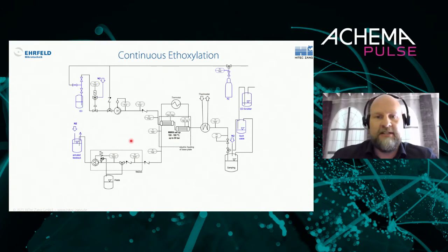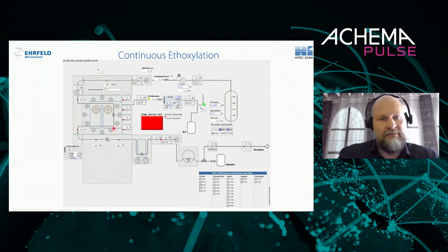The next slide shows a project we set up for ethoxylation, which may not look very complex in terms of hardware but is one of the most complex projects we've had in terms of process control and automation. We have our reactor with residence time extension, a feedstock feed, and an ethylene oxide feed. The ethylene oxide feed is controlled by a pneumatically driven valve — it is critical that no EO reaction can occur if anything goes wrong in the system.